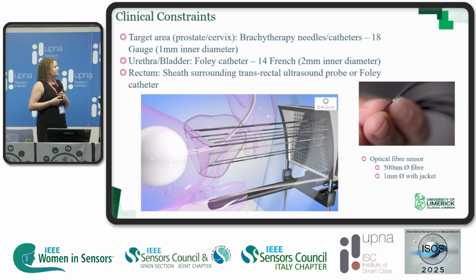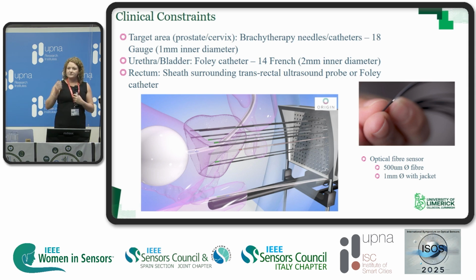So, looking then at our clinical constraints, we have various things, but really what limited us was the Foley catheter dimension. For men, the maximum diameter is a 14 French Foley catheter. The inner diameter of the port opening to allow our sensor to pass through was 2 millimeters. So if we wanted to have the 3 optical fiber sensors in here, it limited our sensors to being a 500 micron fiber sensor with an outer jacket of 1 millimeter.